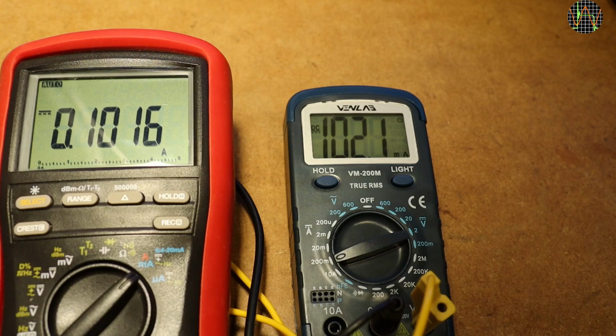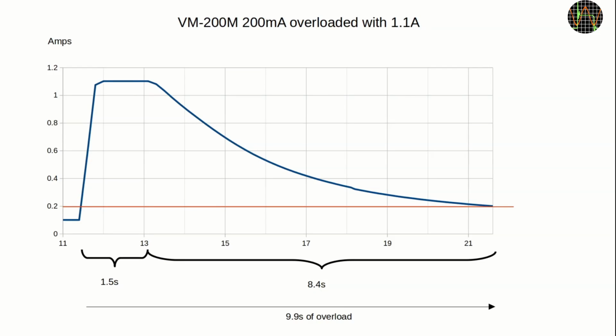At this moment I reduce the current back to the original 100 milliamps. The meter takes a bit to recover because the PPTC needs to cool down first before the current resumes its original value. The recording of the BM869S shows that it took 1.5 seconds during which the VM-200M was exposed to the full overload current. Then the PPTC started to limit the current progressively, and over the next 8.4 seconds it dropped below the 200 milliamp threshold, so the meter wasn't overloaded anymore. The datasheet we looked at earlier was not far off. While the PPTC responded after just 1.5 seconds, it took a total of 9.9 seconds for the current to be reduced below the 200 milliamp mark.